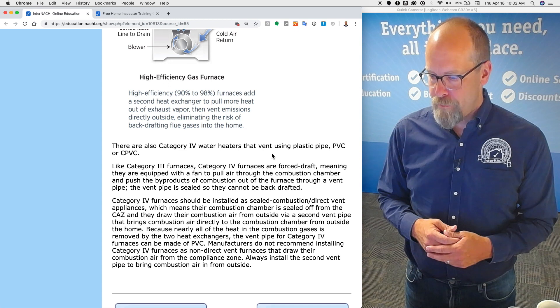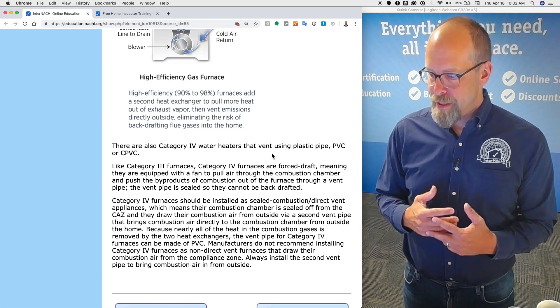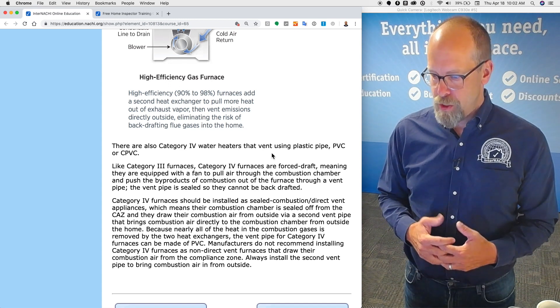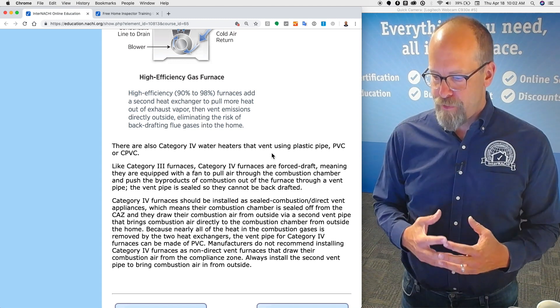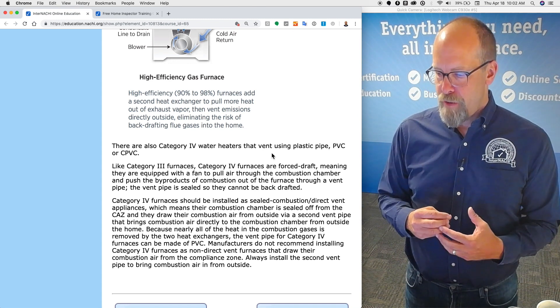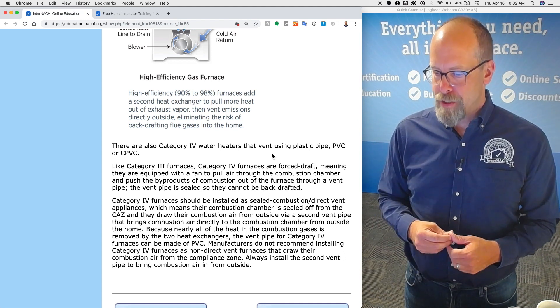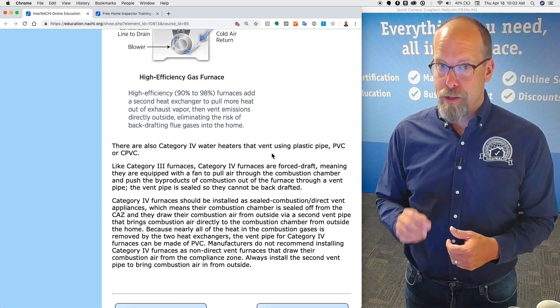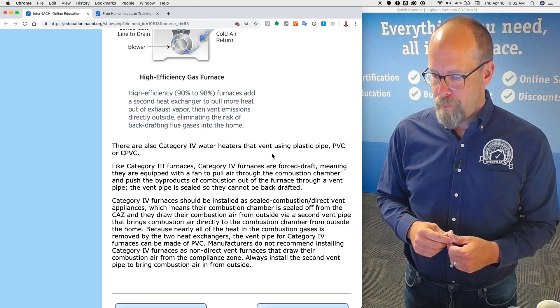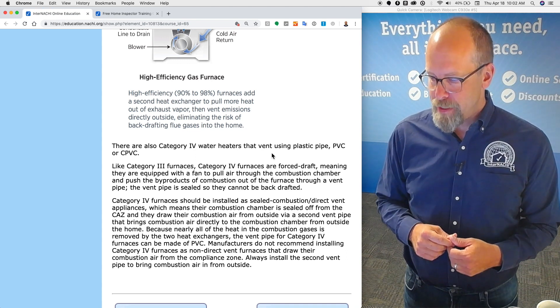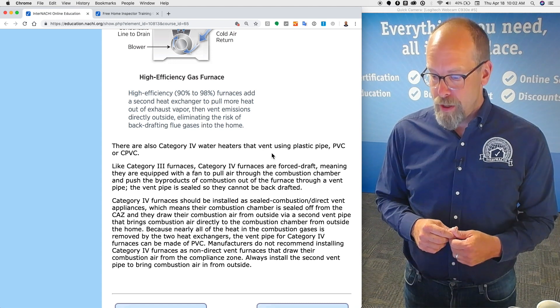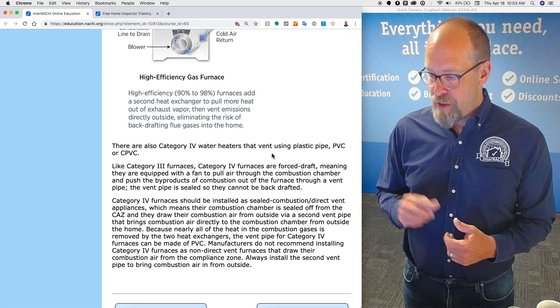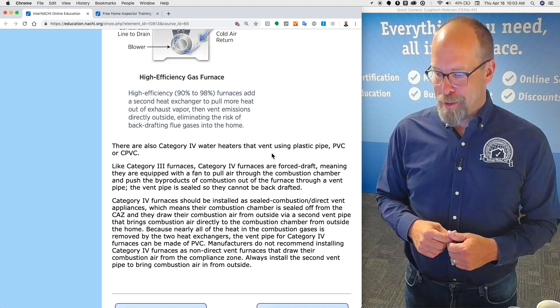Category four furnaces should be installed as sealed combustion direct vent appliances, which means their combustion chamber is sealed off from the CAZ, and they draw their combustion air from the outside through a second pipe that brings combustion air directly into the combustion chamber from the outside of the home. Because nearly all of the heat in the combustion gases is removed by the two heat exchangers, the vent pipe is made out of plastic.